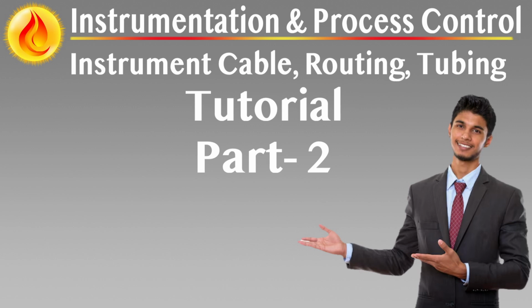Protection for instruments and cabling in exposed areas. For instruments installed in unprotected locations, such as tank farms, tower tops, or elevated pipe racks, supplementary lightning protection is mandatory. These installations must be identified during the detailed engineering stage and equipped with surge protection devices at both ends of the signal path. Protection is required whether the threat is direct, e.g. elevated sensors, or indirect, e.g. cable runs across open terrain.